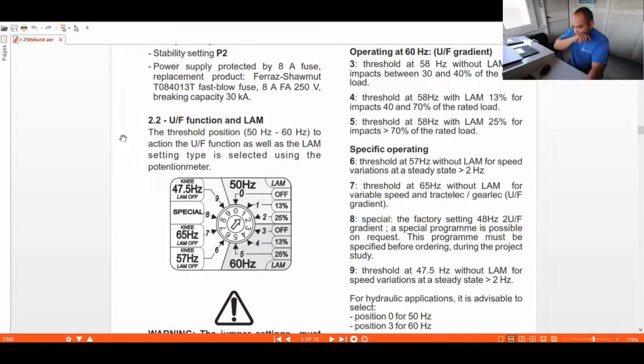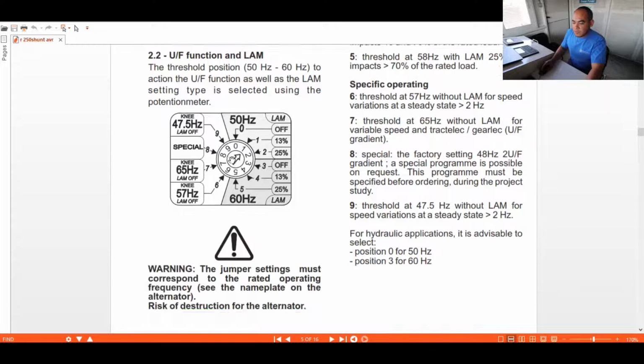Here are your under frequency functions and the LAM thresholds for positions 50-60 Hz, as well as the under frequency actions, and the LAM setting, which is selected using the potentiometer.